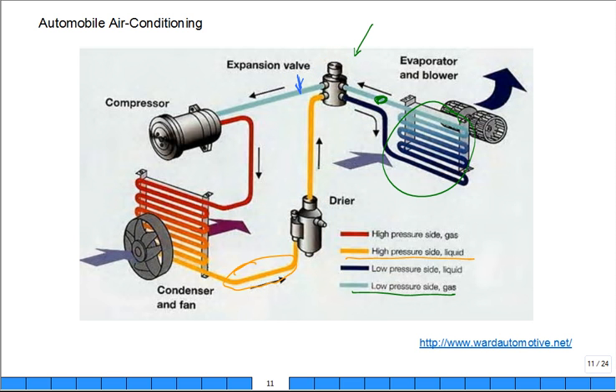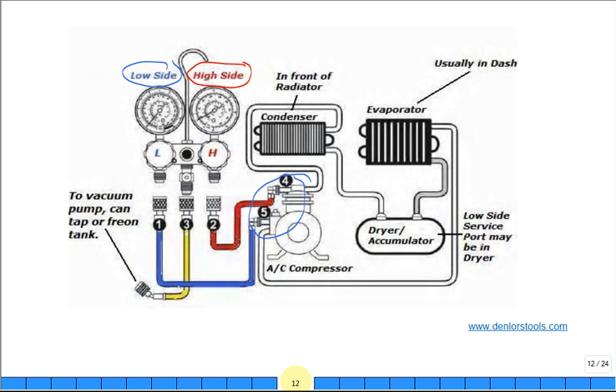This is the low pressure right here. You would tap into it as it goes back toward the compressor, and then the high pressure right there. So you have the taps typically close together so that they can find them easy and attach their gauges. And they can diagnose: oh, you have too much refrigerant, too little refrigerant, etc. Then they can hook up and they can charge the system or pull a vacuum and work on it.